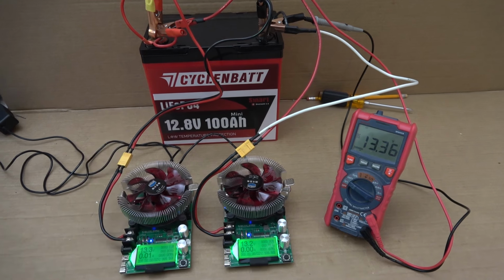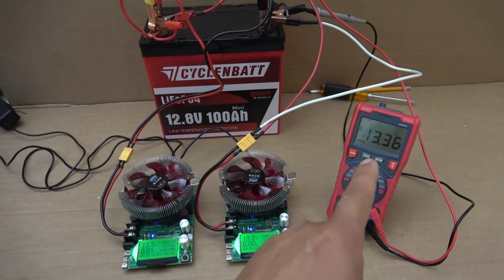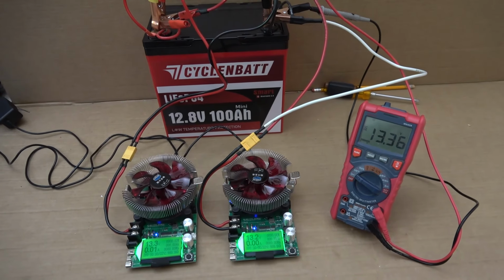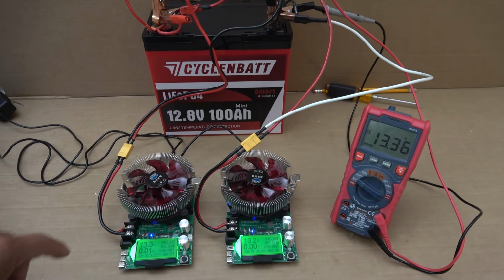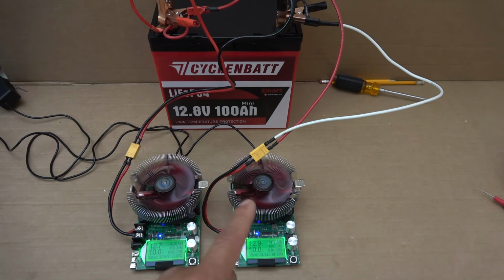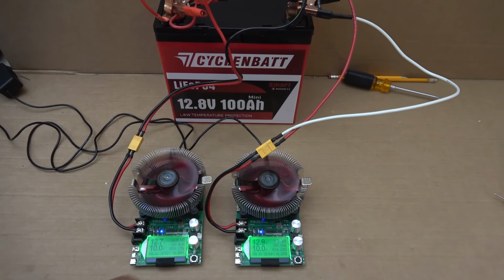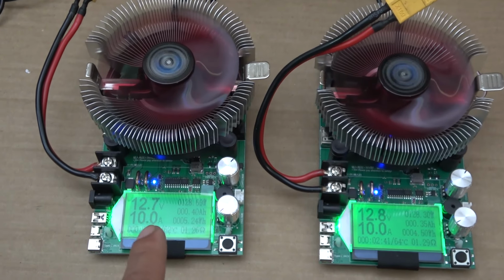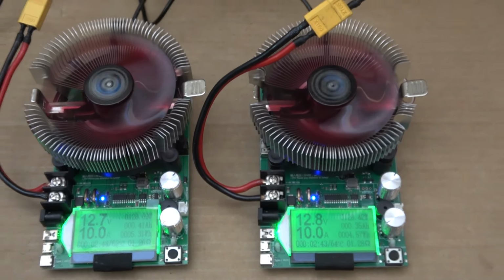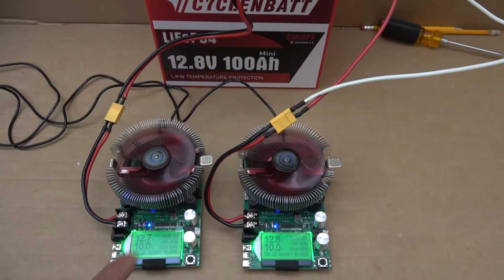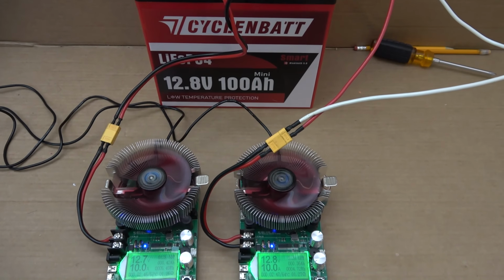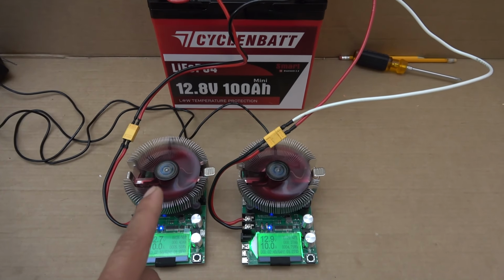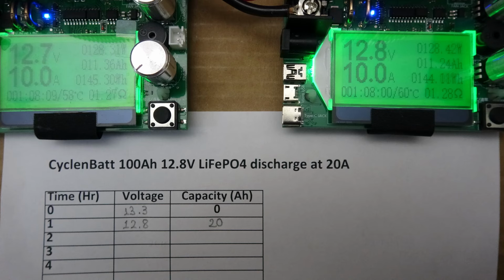I have charged the battery to 100%. The battery now reads 13.36 volts. It's time to do a capacity test. I have 2 capacity testers here, each discharging at 10 amps, for a total of 20 amps. The battery is rated 100 amp hours, so this will take about 5 hours to finish.